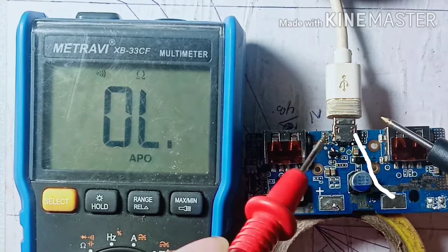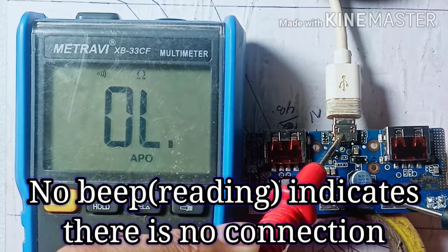I'll check whether this ground has the same potential difference as the B minus ground - they should be connected since both are grounds. To check this I'll probe with my meter. I hear no beep or reading, indicating there's no connection. So I'll simply install a jumper cable between the two terminals.